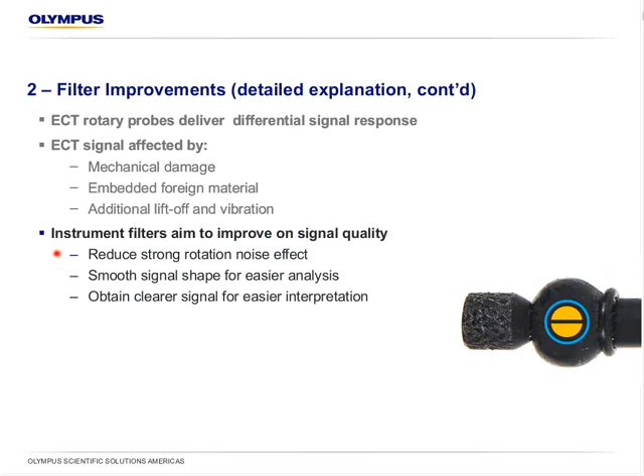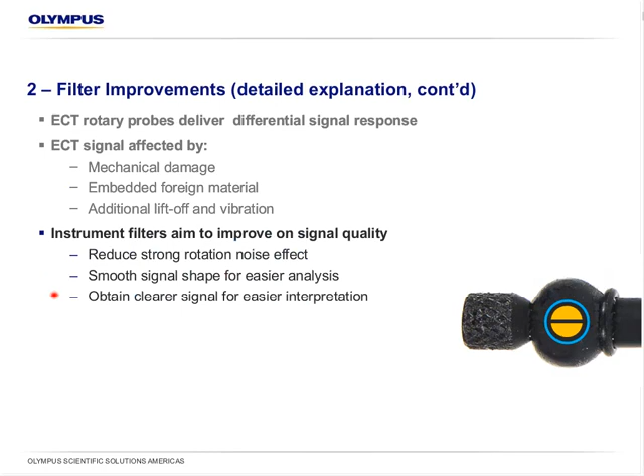So the eddy current rotary probes deliver differential signals. We just saw that. The eddy current signal is affected by mechanical damage, embedded foreign material, additional liftoff and vibration. And the instrument filters aim to improve on signal quality. Basically, one of the main purposes of filters is reducing the strong rotation noise, basically the noise that comes from the test itself. Also, one use of the filter is to smooth up the signal shape for an easier analysis. And finally, we basically try to achieve a clearer signal for easier interpretation.